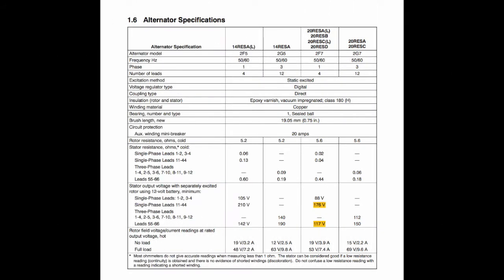Down here it shows you stator output voltage with separate excitation voltage using a 12 volt battery. So we did it with a 12 volt battery, and right here they're giving us on leads 1 and 2, 3 and 4, 88 volts. We're reading across 11 and 44, and that shows us 11 and 44 is 176. We had a 177. That's good. On 55 and 66, our power boost winding, it's saying 117, and we had right around 117, 118. So that all checks out.